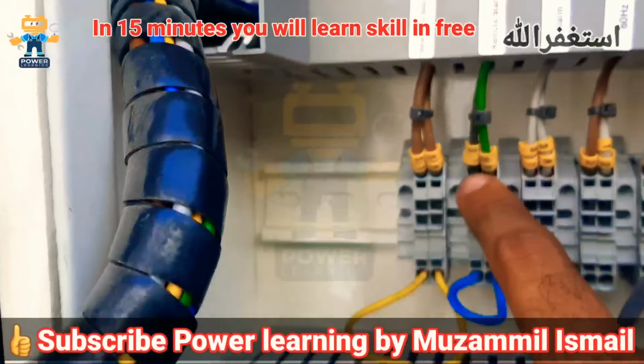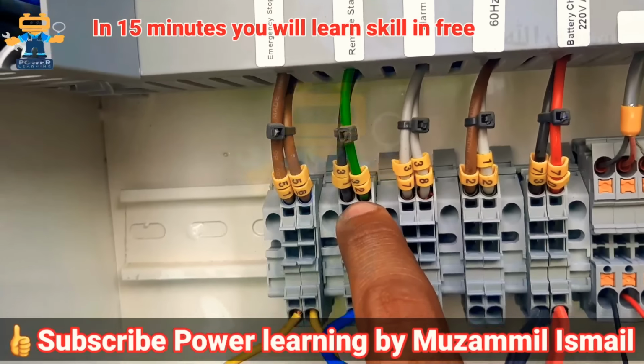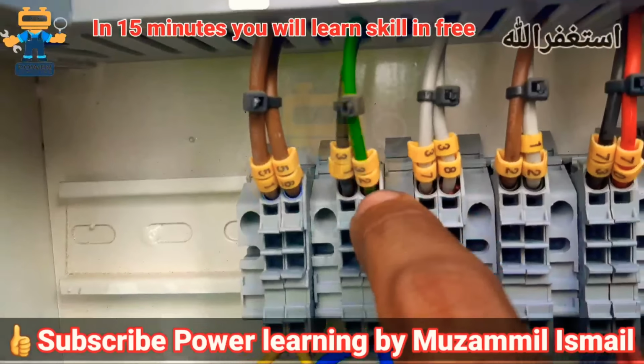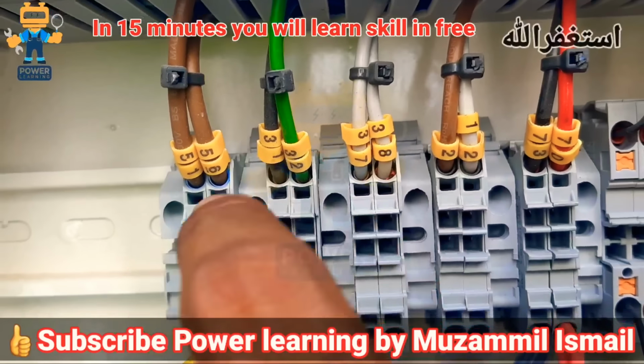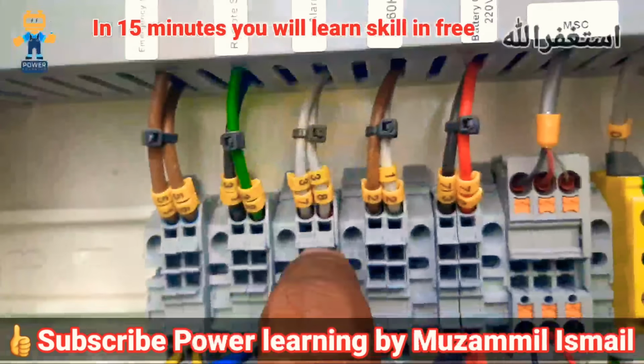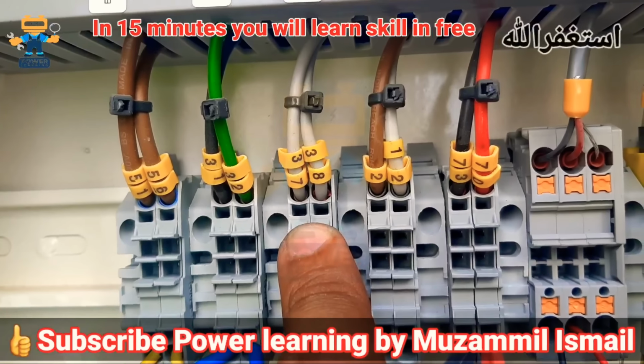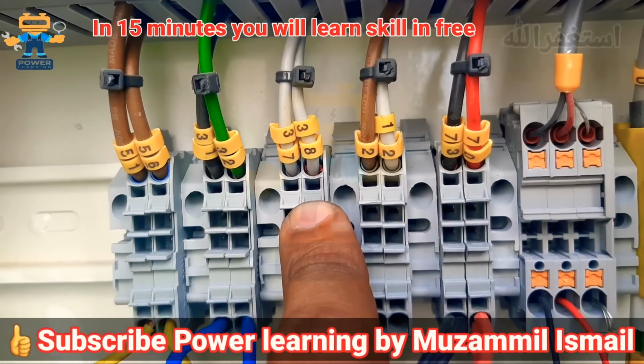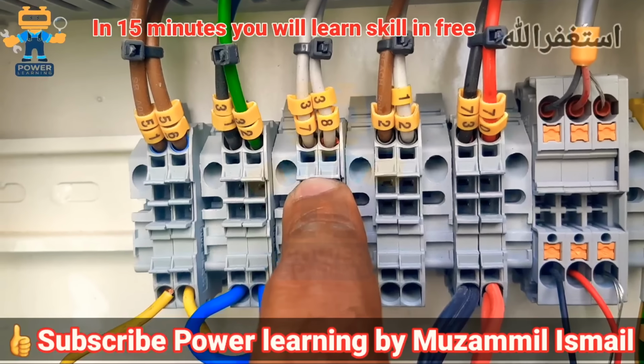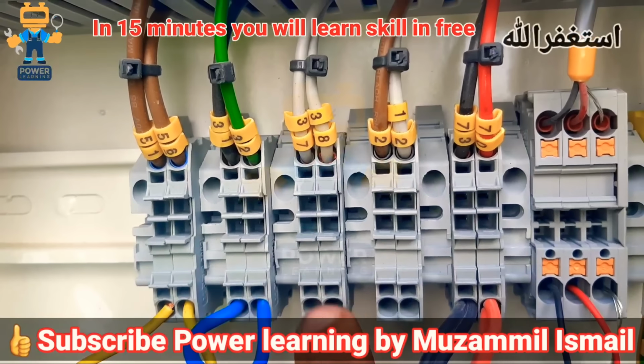cable which is connected from our remote start. As you see here, this remote start has a number 32 wire. Okay, so this is remote start, and here we have emergency stop. Okay, and here we have alarm. If we are connecting this with any external alarm, or to stop the generator from the BMS room, we will connect the cables here.